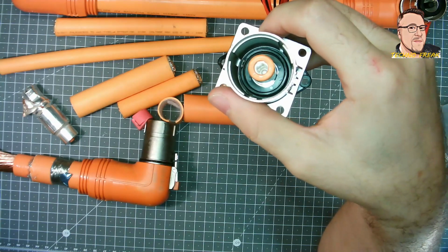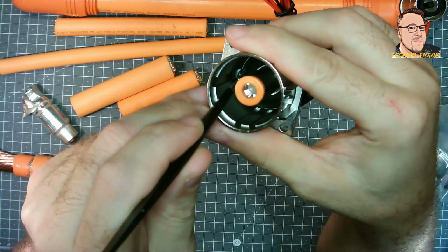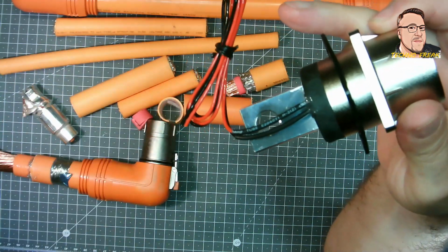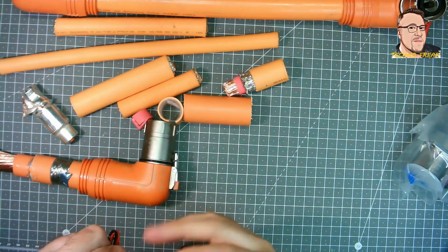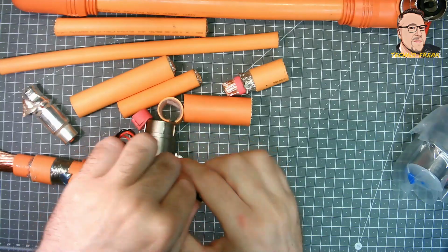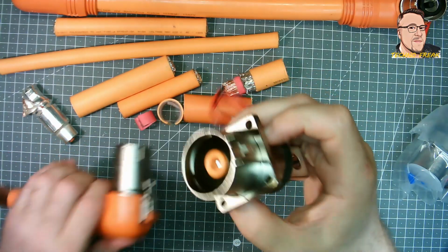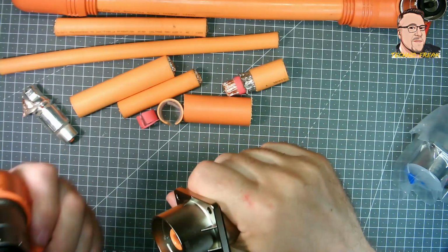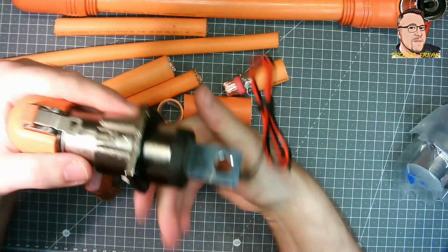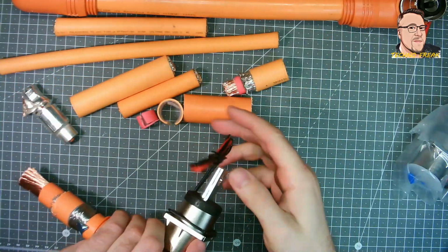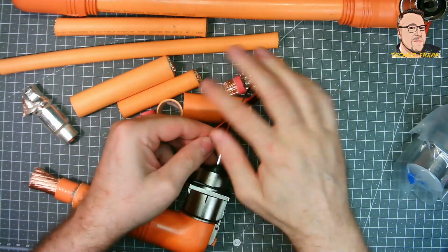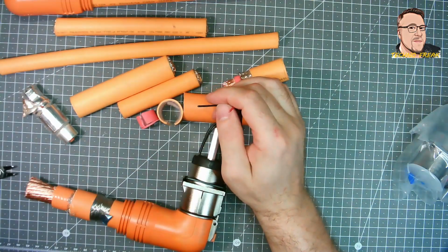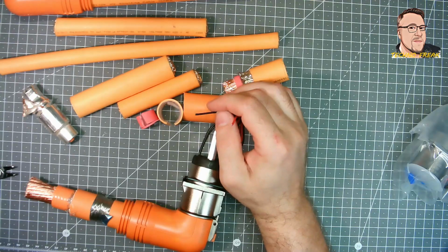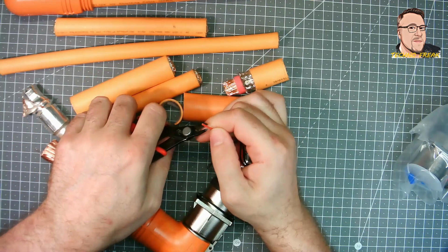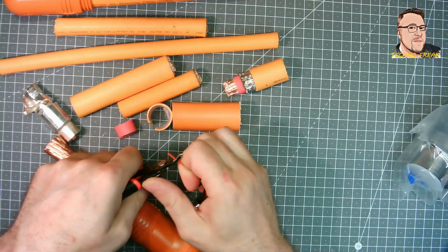And here, deep inside the connector, you can see two small pins. That's the HVIL. HVIL is a special electrical loop which is closed when the connectors are connected. When any connector is disconnected, that HVIL loop will be open and send a signal to the control to open the contactors, to avoid unplugging the connector under load, because that could create a lot of arcing, especially with DC current. And now I will show you HVIL in action.